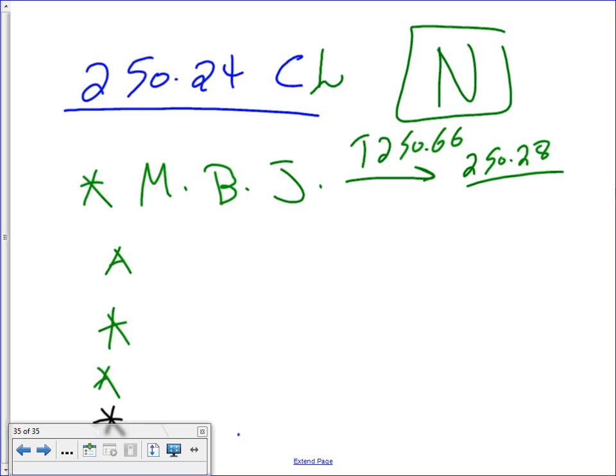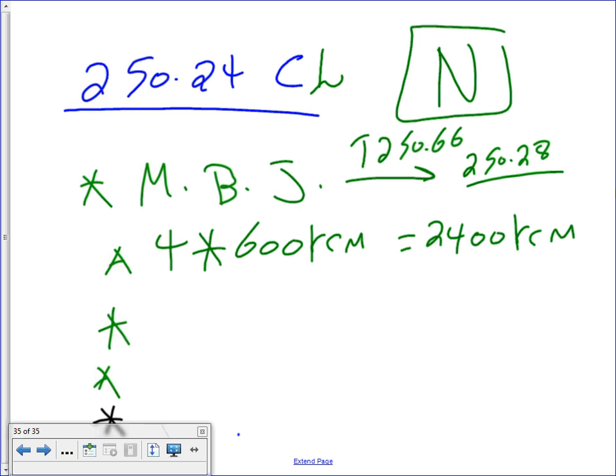The way you size this one, guys, you're going to take 4, multiply this one by 600. You guys remember that 600 kcmil? That will get you 2400 kcmil. Then you're going to multiply 2400 kcmil by 0.125, 12.5%. This is coming from 250.28.